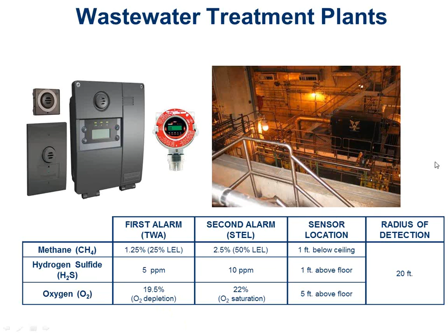MRI rooms are a really common one as well. In these rooms, we have to measure for lack of oxygen. So it's a very common sensor. I don't know if it's a code required thing or just a standard good practice that everybody who runs an MRI room does, but every one I've ever done has an oxygen sensor in there. Oxygen, we measure above the floor. It's a little bit heavier than just plain air because, as you know, plain air has other things in it. We want to make sure we don't have too little oxygen in most of these cases.